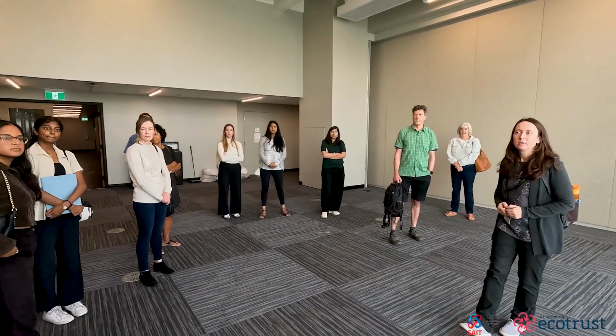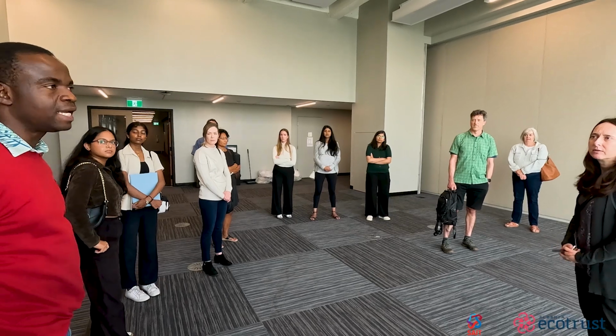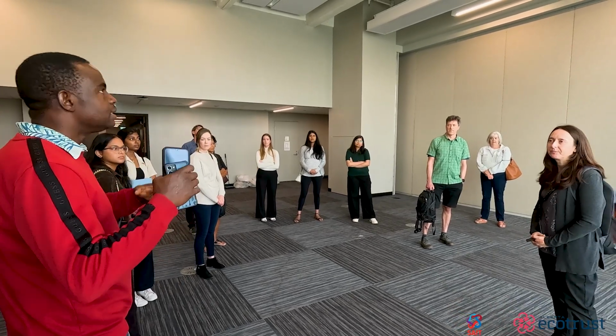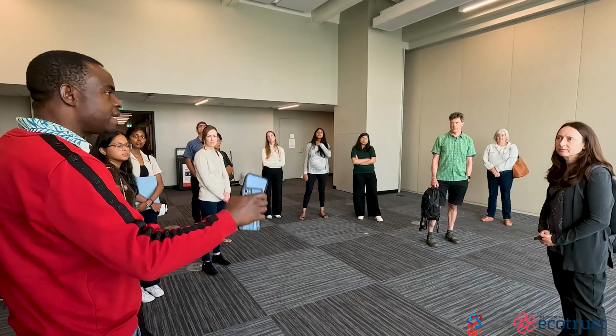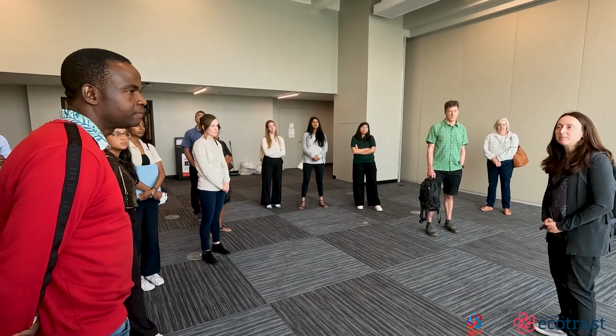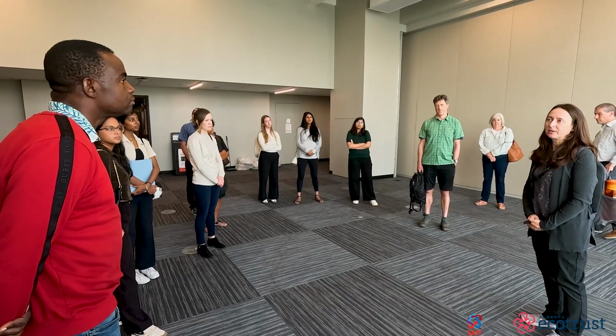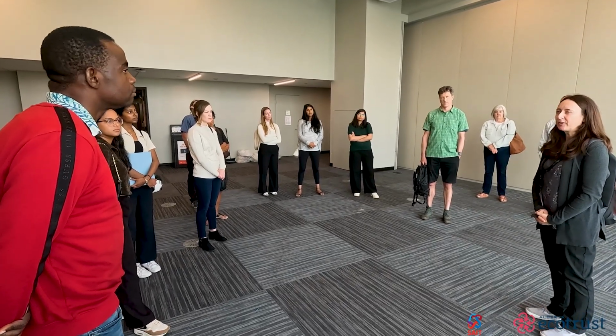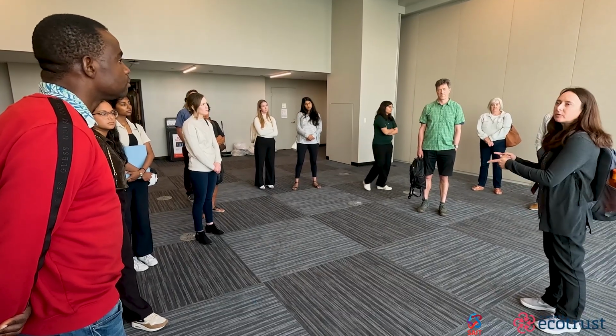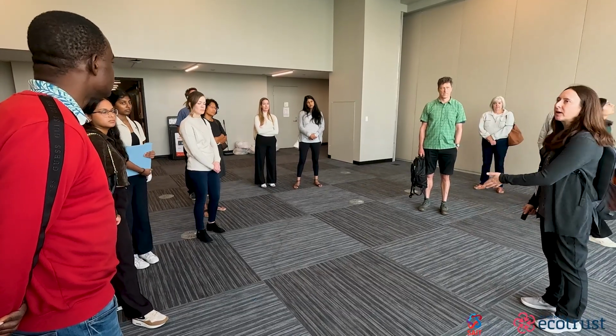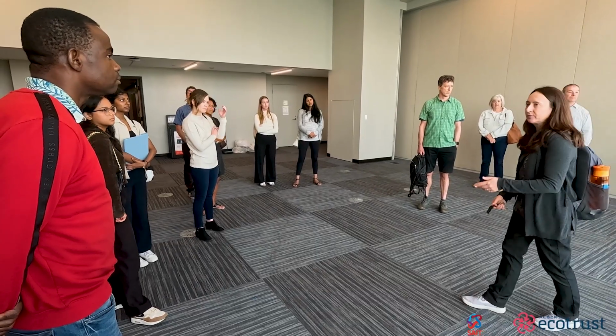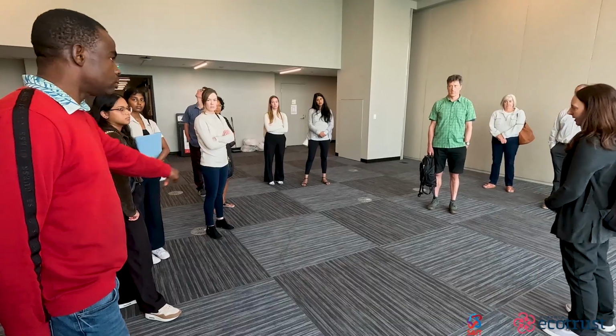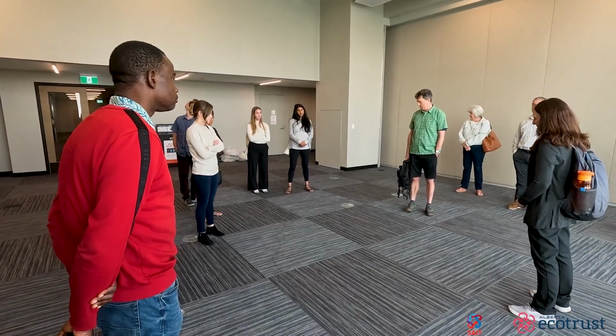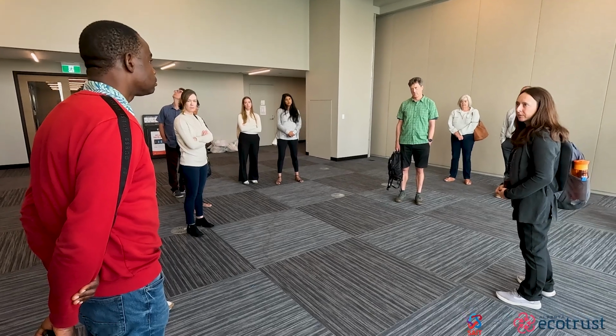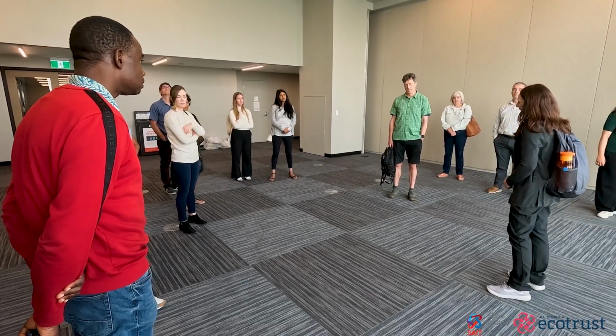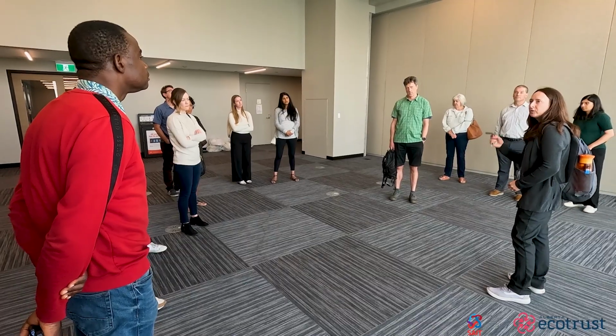Do people complain about, because the air is not filtered, right? It's outdoor air - that's right, there's no filtering of the air coming in. Does it make the space dusty? It could, yeah, it could make it smoky, it could make it dusty. That's why when there's wildfire smoke in effect, we typically rely on mechanical systems more so we can filter through dedicated outdoor air filters. The dedicated outdoor air system will provide filtered air, and that comes in the underfloor, so it's slow moving air - not so much for cooling, more for ventilation, and we do the cooling with the radiant panels.